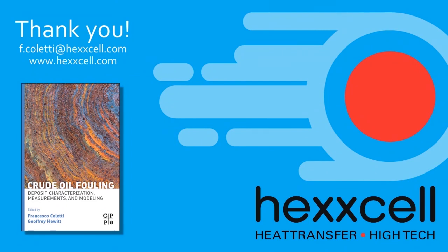So, for example, in the application I showed today, heat exchangers at very high temperature, it's unlikely that you'll find a coating that will work. But in other applications, they can be used very successfully. For example, I'm aware of some pilot studies done on offshore platforms. Clearly, opening up the plate heat exchangers there is a very difficult exercise, and they're at lower temperature, so although the environment is quite harsh, there are coatings that work pretty well for that specific application. So it really depends on the application, but if they can be applied, they can be a very good solution.